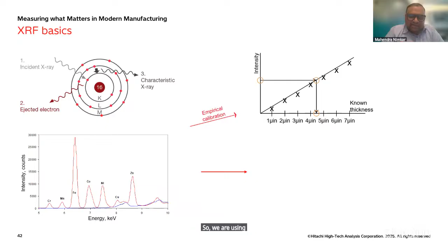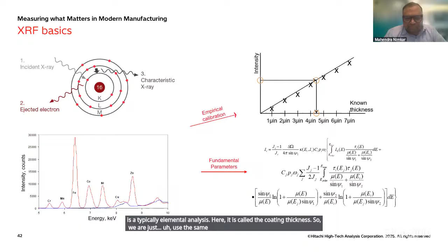So we are using the same thing in converting this calibration into the thickness. We are using this intensity to measure the thickness. It's again the software, and there are a lot of software and algorithms, but let us not go into that. What I'm trying to convey is that the higher the coating thickness, the larger the peak. The same applies during coating thickness. The earlier algorithm for bulk analysis, or elemental analysis for RoHS, is typically elemental analysis. Here it is called coating thickness. So we just use the same XRF with different software.